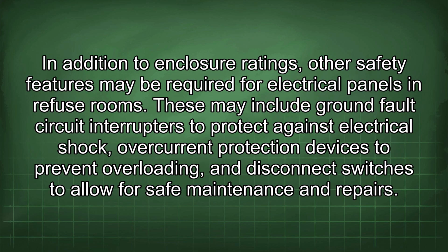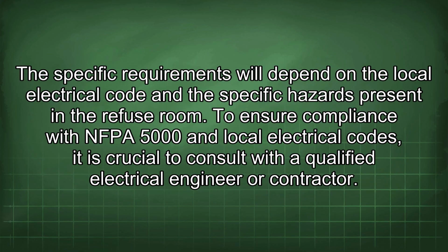In addition to enclosure ratings, other safety features may be required for electrical panels in refuse rooms. These may include ground fault circuit interrupters to protect against electrical shock, overcurrent protection devices to prevent overloading, and disconnect switches to allow for safe maintenance and repairs. The specific requirements will depend on the local electrical code and the specific hazards present in the refuse room.